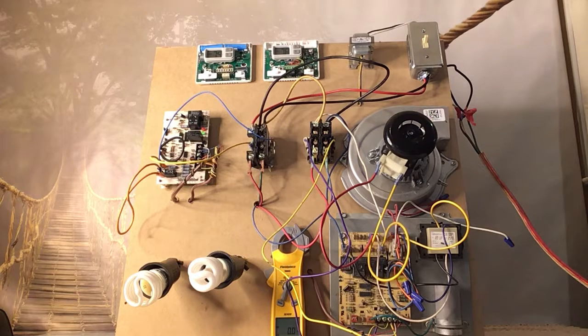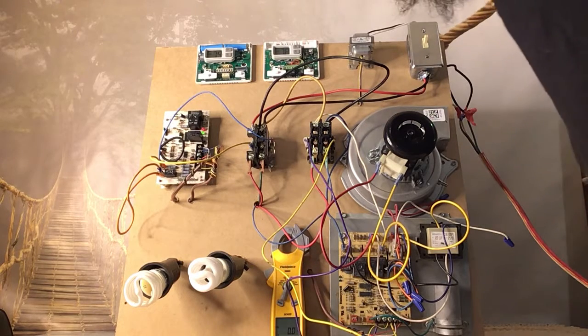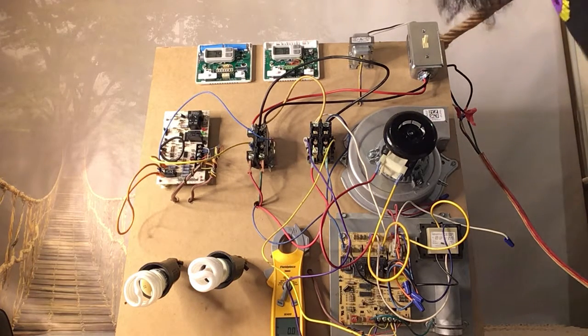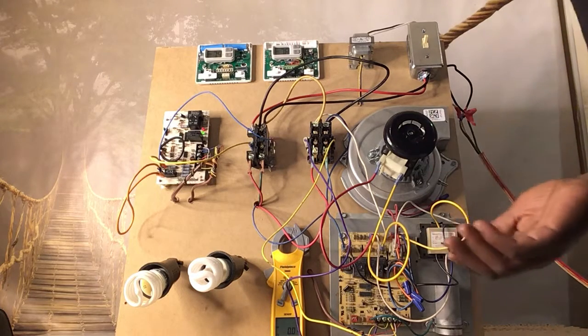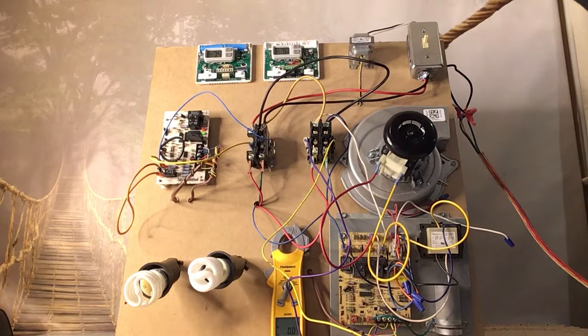And what you will find underneath of them both is a common wire. You will find a red wire for 24 volts. You will find a blue or an O, which represents the reversing valve. You will find a yellow, which represents cooling. You will find a green, which represents your fan. And then you will also find a white, which represents heating or emergency heat in this situation, if we're speaking of a heat pump. And just in a regular straight AC system, you'll find some of the same similar wires. You'll have a green for the fan. You'll have a yellow for the air conditioning side. Your white wire would typically be used for heating, and then your red is where your voltage actually is.